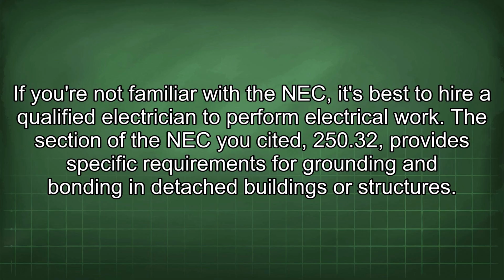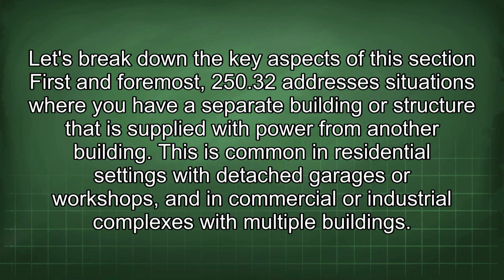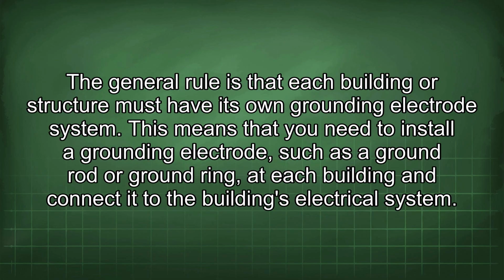The section of the NEC you cited, 250.32, provides specific requirements for grounding and bonding in detached buildings or structures. Let's break down the key aspects of this section. First and foremost, 250.32 addresses situations where you have a separate building or structure that is supplied with power from another building. This is common in residential settings with detached garages or workshops, and in commercial or industrial complexes with multiple buildings. The general rule is that each building or structure must have its own grounding electrode system.